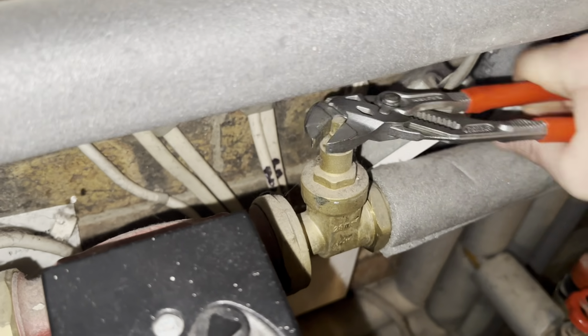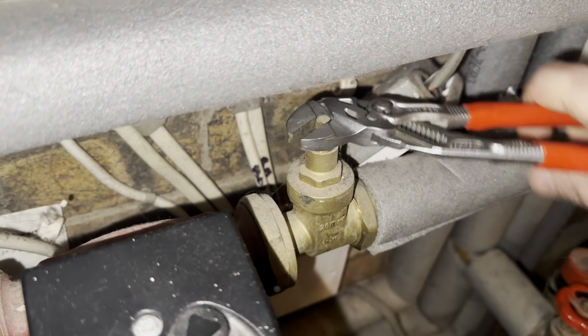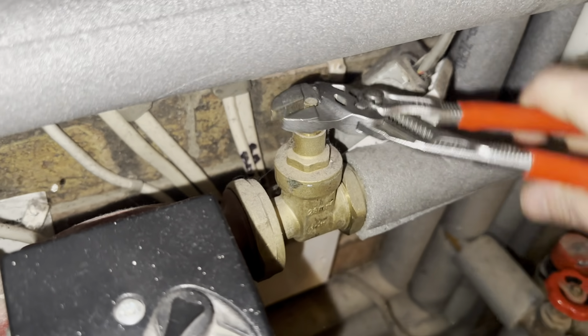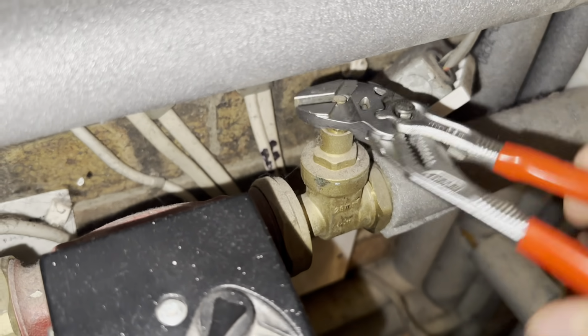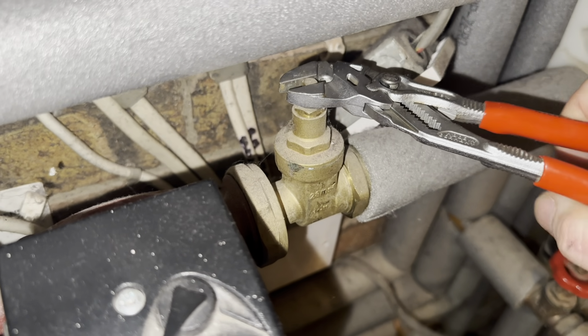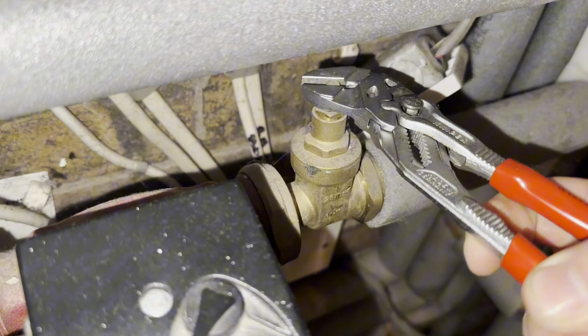What I'm going to do is whip that pump head out, see what's going on inside there, test that out, eliminate all these main parts - now the motorised valve, make sure that's moving over, no blockage, because we've got heating on the building, but there's certain areas not working.